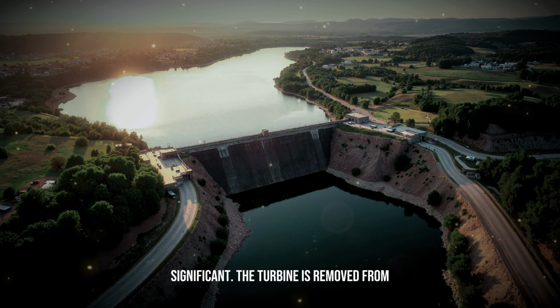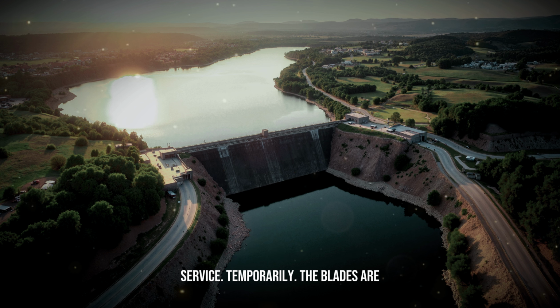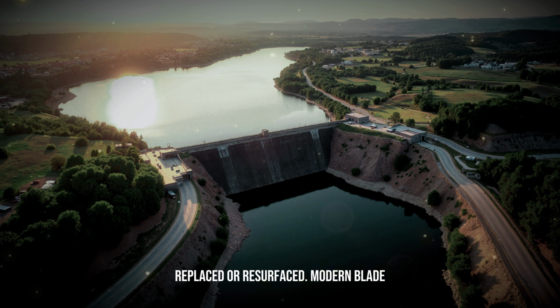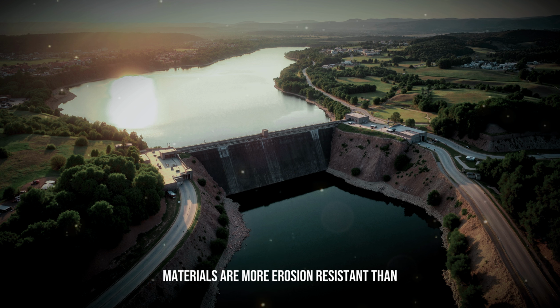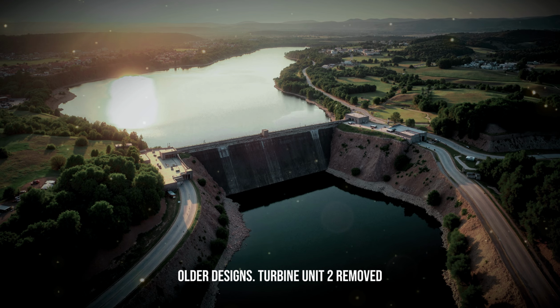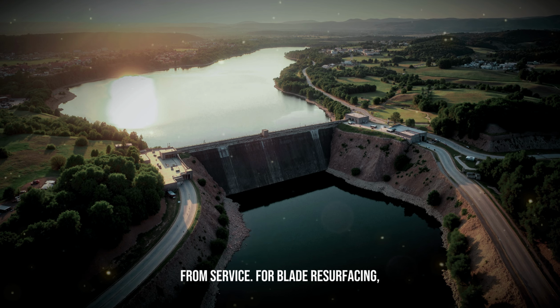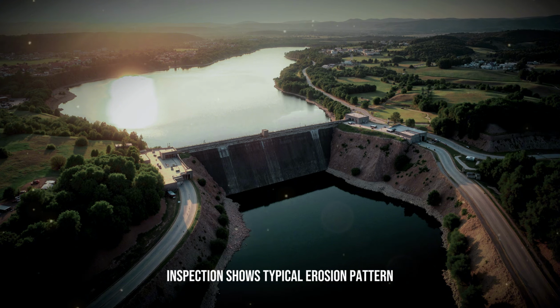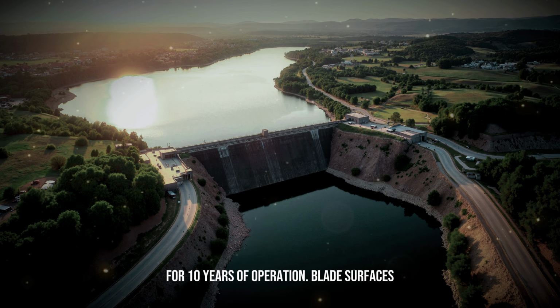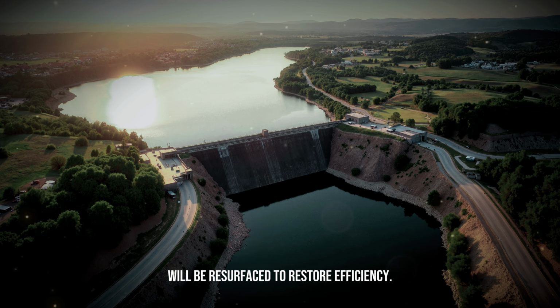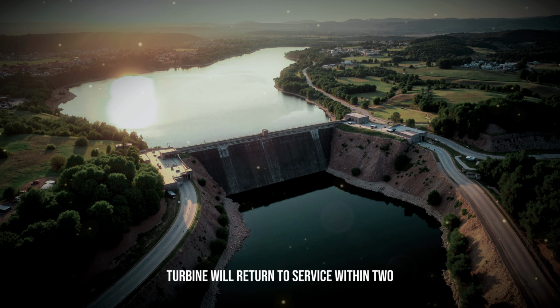The turbine is removed from service temporarily. The blades are replaced or resurfaced. Modern blade materials are more erosion resistant than older designs. Turbine Unit 2 removed from service for blade resurfacing. Inspection shows typical erosion pattern for 10 years of operation. Blade surfaces will be resurfaced to restore efficiency. Turbine will return to service within 2 months.